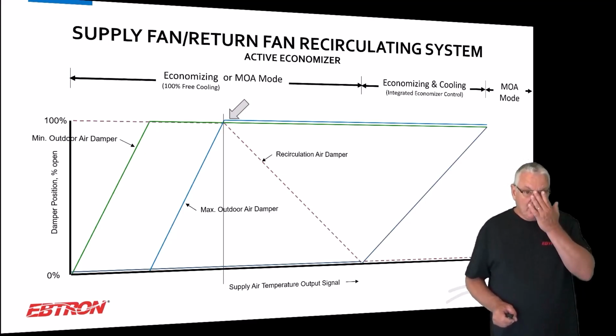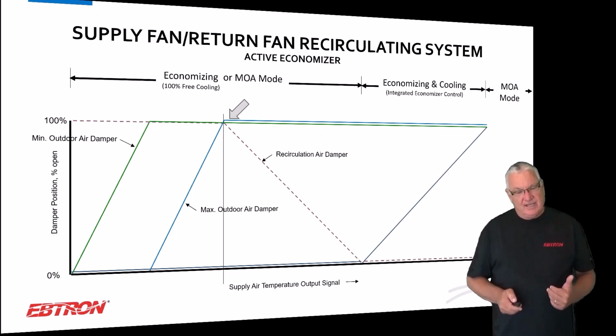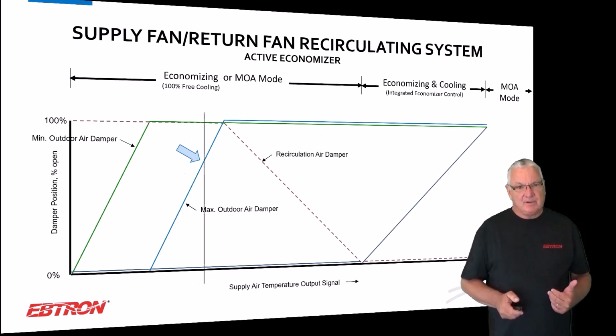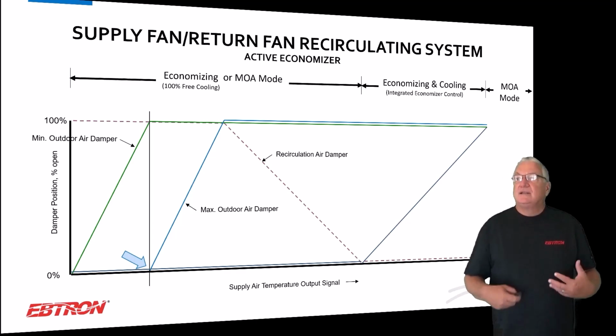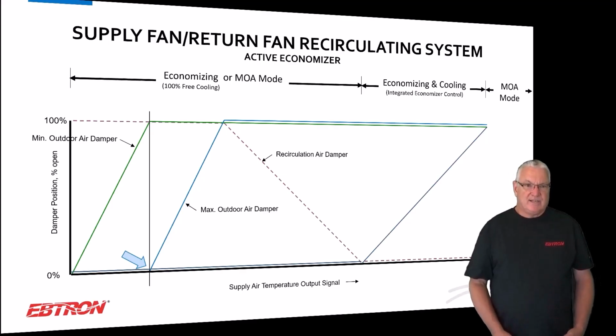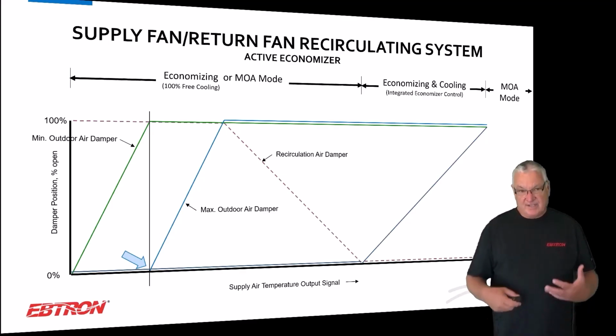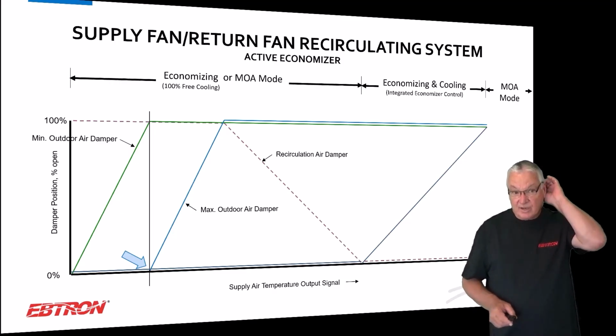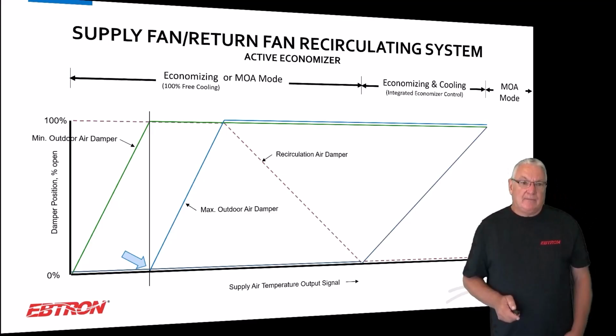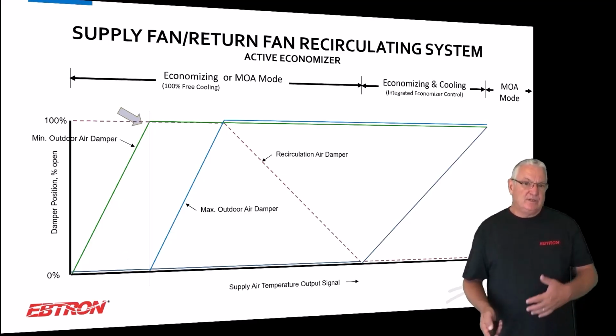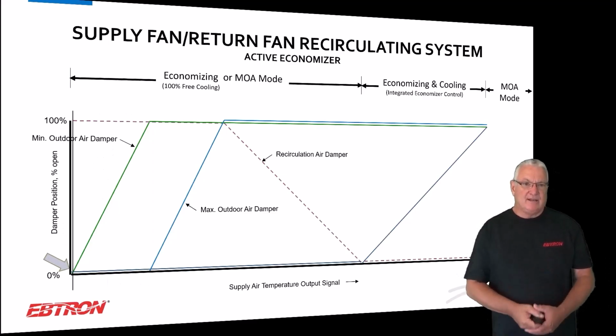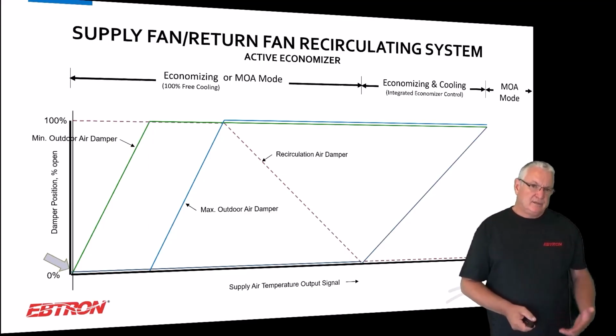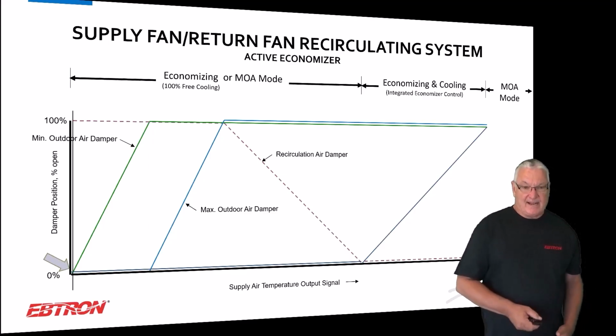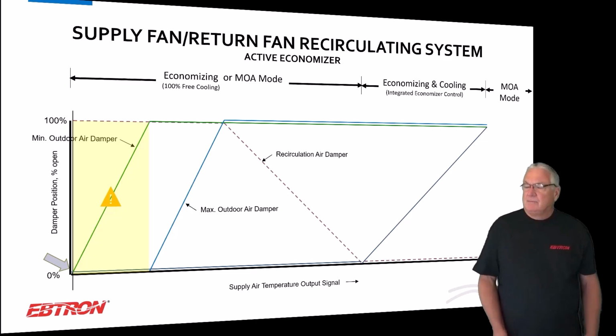Okay, but what happens is as you modulate down now, this max damper, and it finally gets closed, now your outside airflow measurement device is doing what it's supposed to do. If you've set this up right, it is exceeding the max. Your design max, and then you would start to modulate this down. And again, you'd get to a point where you would potentially have to get out of economizer. Just got to watch the flow rates again.